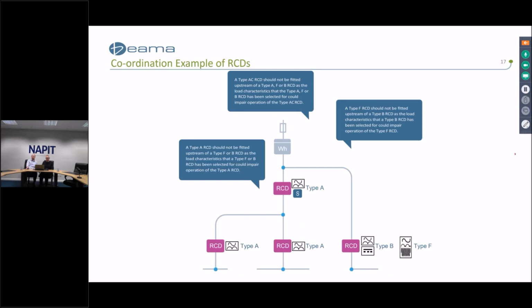So again using the middle leg, if we needed a type F or type B, it should go upstream with the type A downstream. You can see that for the specific applications where type F or type B is needed, it comes off from the origin of the circuit rather than through another RCD. So it's very important that the correct coordination is applied. So basically, the upstream RCD must be at least equal or higher than the downstream RCD.